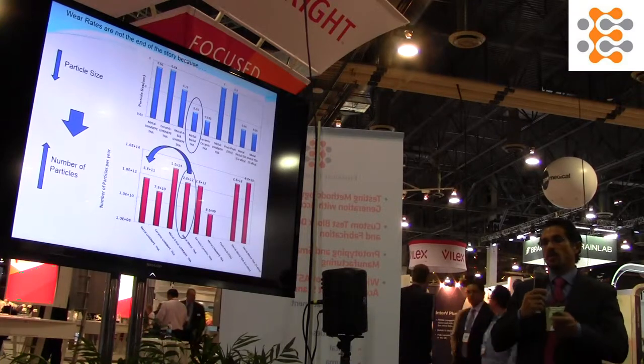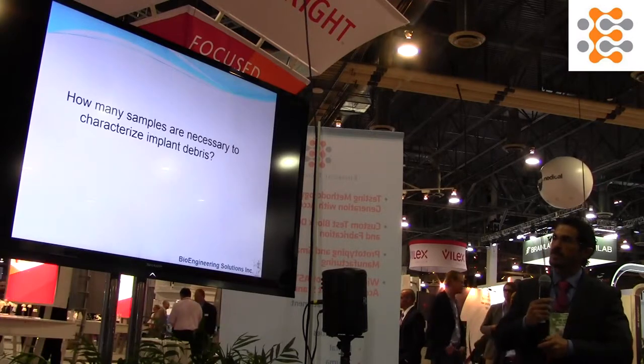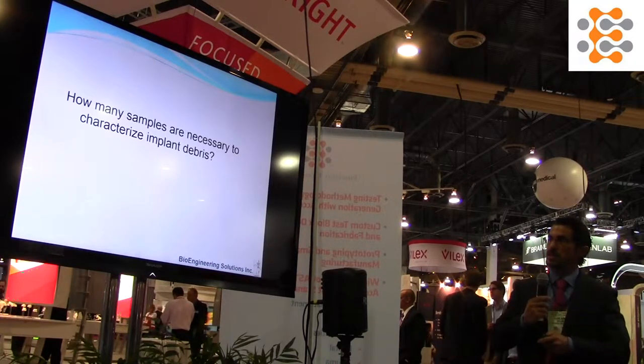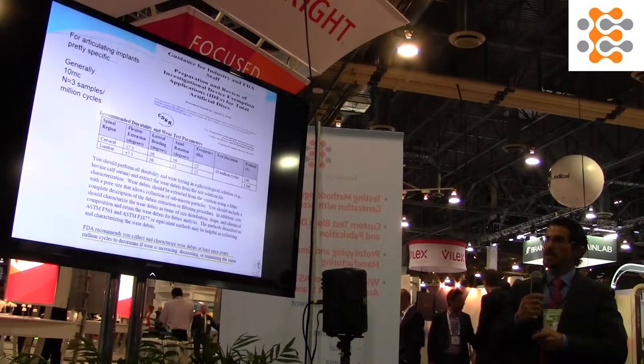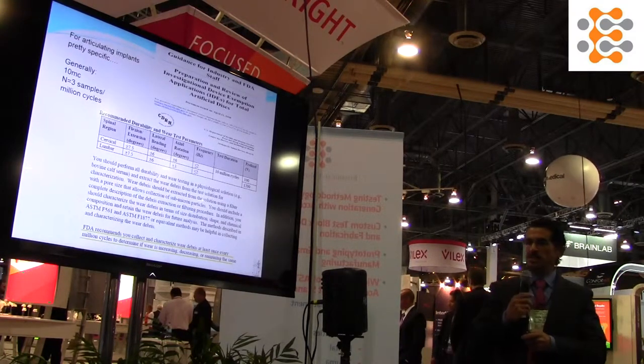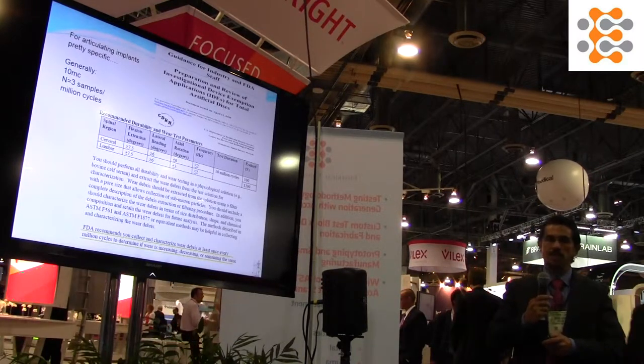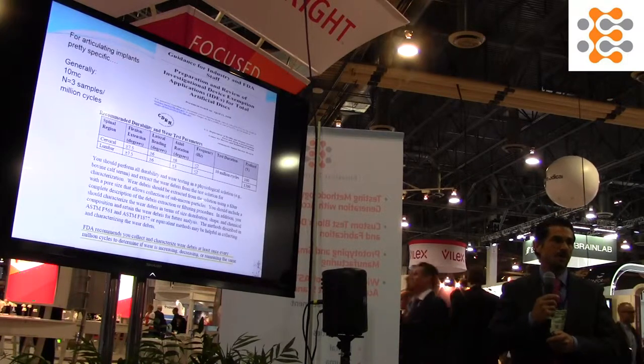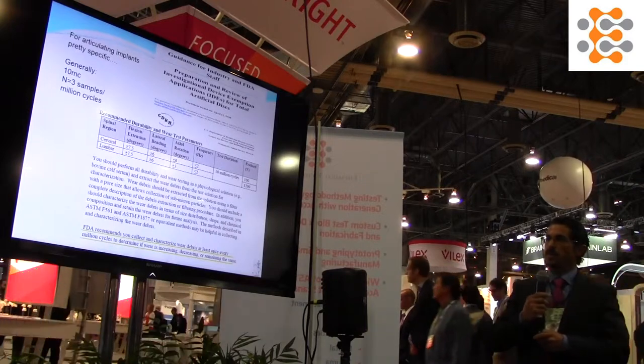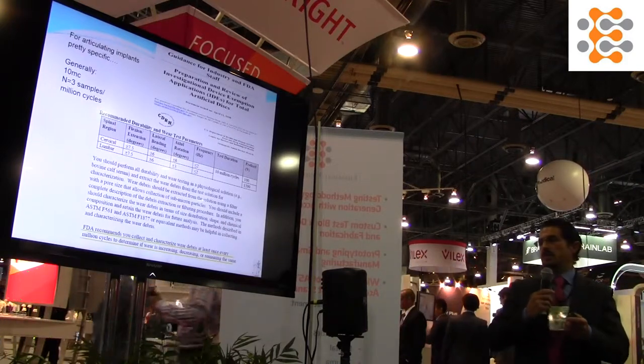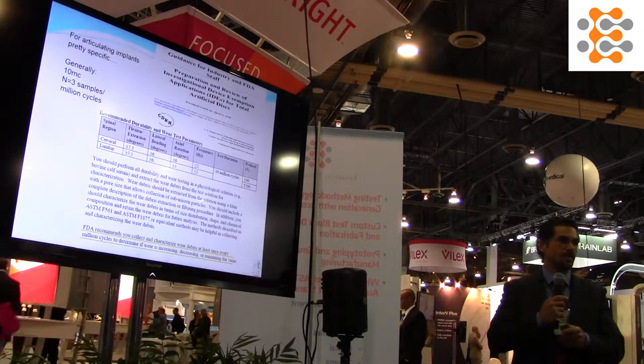The order of magnitude more particles could contribute to that failure of the implant over time. How many samples are necessary? It's not generally locked into any one particular amount of samples, but my recommendation is three samples at least for doing particle size analysis. That way you can do enough statistics to show that they are different from other implants, from one million cycles all the way up to ten million cycles.